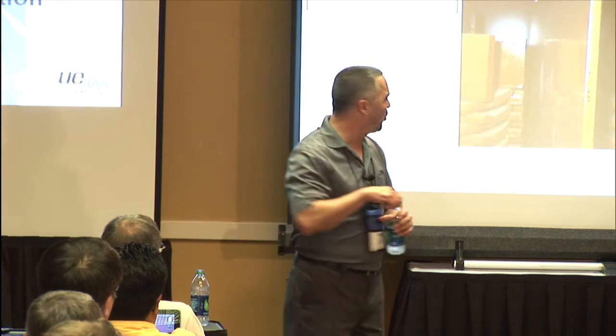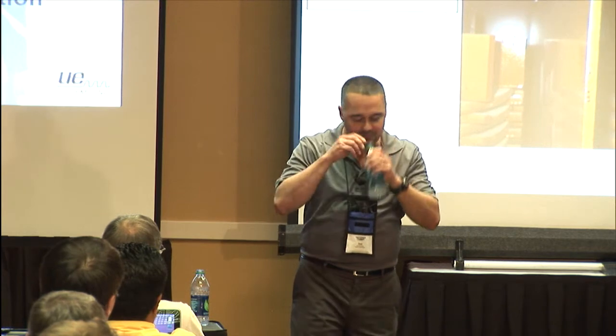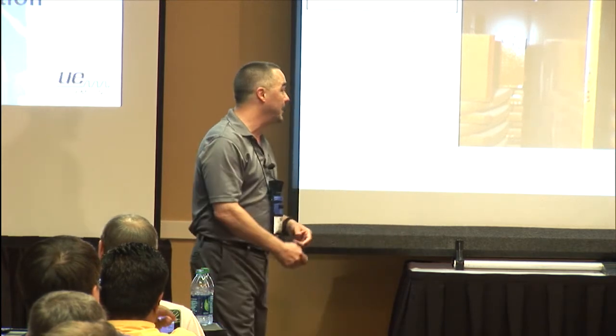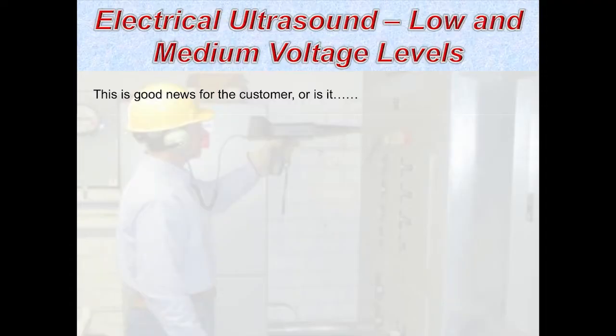From a visual inspection standpoint, what do you think about the condition of this unit, considering where it's located? It's a little dusty, but other than that, for 5 years old, it looks pretty darn good. There's no evidence here that the insulating system might have been overheating. The core doesn't look at this point like it's overheating. We exceeded the dynamic range of that infrared camera, but so what? The cores run hot - I'm not worried about that. That's good news for the customer, isn't it?